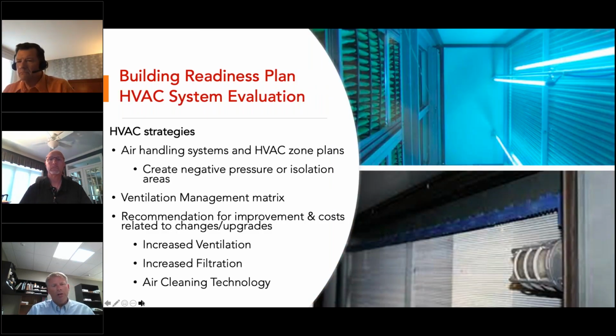So I'm going to start by talking about how we handle this. Step one is really to develop a building readiness plan, which is recommended by ASHRAE. Some of you may know that ASHRAE came out last year with a checklist. I think it's up to like a 200-page document now. They've updated it a couple of times over the past year. It means looking at your air handling systems, your HVAC zone plans, and whether you need isolation rooms or negative pressure areas. We've developed a ventilation management matrix, which takes a number of things into account: outside air, your existing filters, the sizes, the MERV ratings, and developing that matrix for essentially the entire building on one 11 by 17 plan that can really help develop the recommendations. And some of the recommendations we've come up with match what ASHRAE comes up with.